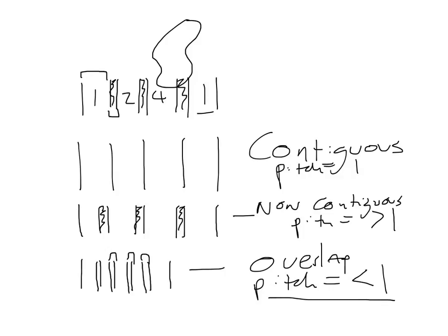Overlapping slices are important when doing 3D studies — some verification and virtual simulations actually want a pitch with some overlap. The computer can then reconstruct that overlapping information and make sure all the volume unifies. If you need 3D rotations of the anatomy, or volumetric determinations like dosimetry for radiation therapy, you may use a pitch of less than one so there's overlap of information. As the computer averages the linear attenuation coefficients, it gets a better-than-one-to-one ratio — a very accurate reading.